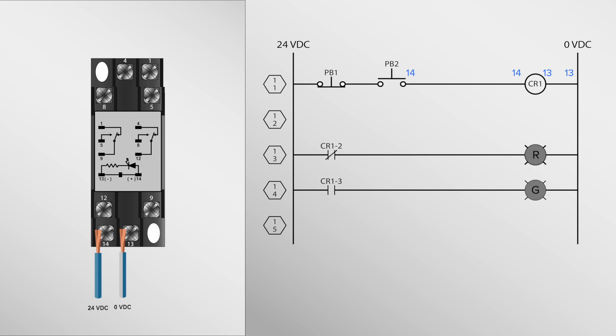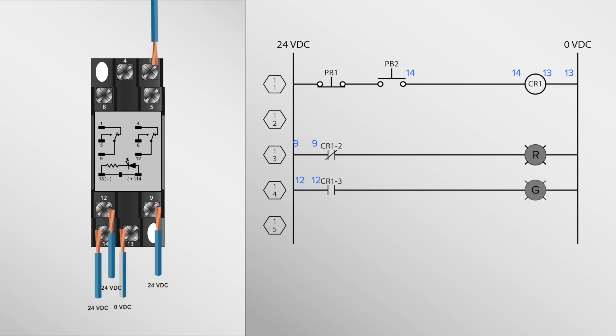To wire the contacts for the indicating lights, you would take positive power to 9 or 12 and take another wire and wire it to 1 or 4 and then connect it to the indicating light. For the green indicating light, since you already have positive power on the 9 or 12, then all you would have to do is wire a wire from 5 or 8 and connect to the green indicating light. The result of the wiring should look like this and will operate like this circuit.